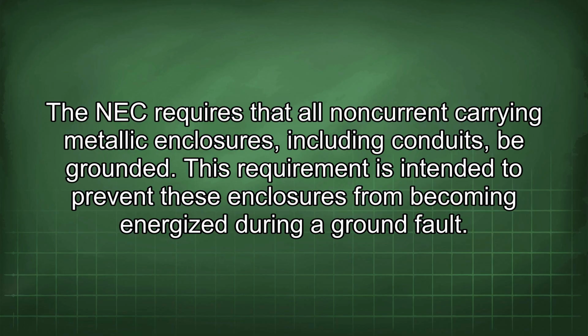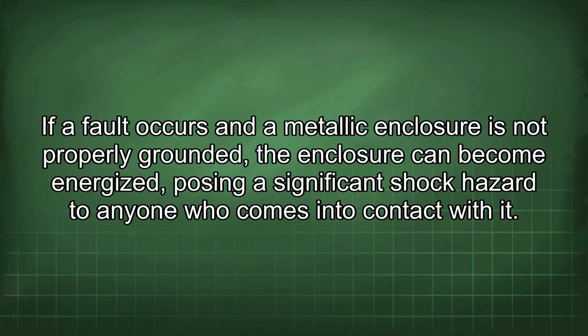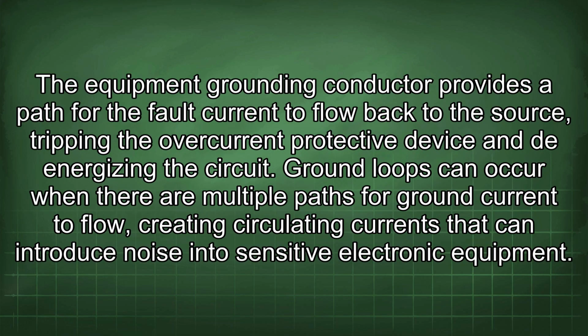The NEC requires that all non-current carrying metallic enclosures, including conduits, be grounded. This requirement is intended to prevent these enclosures from becoming energized during a ground fault. If a fault occurs and a metallic enclosure is not properly grounded, the enclosure can become energized, posing a significant shock hazard to anyone who comes into contact with it. The equipment grounding conductor provides a path for the fault current to flow back to the source, tripping the overcurrent protective device and de-energizing the circuit.